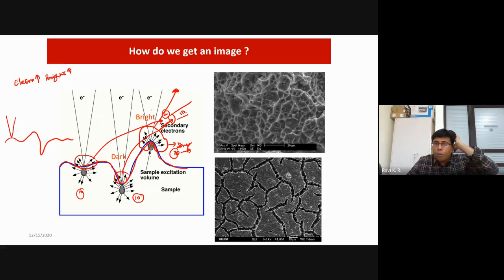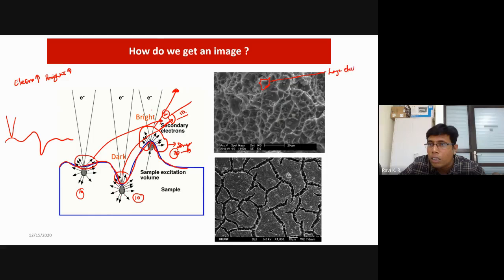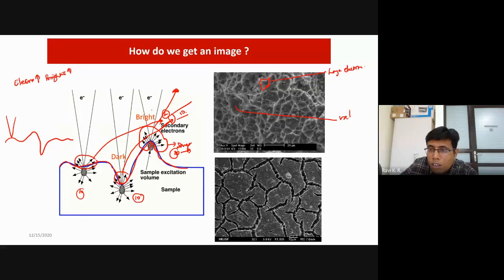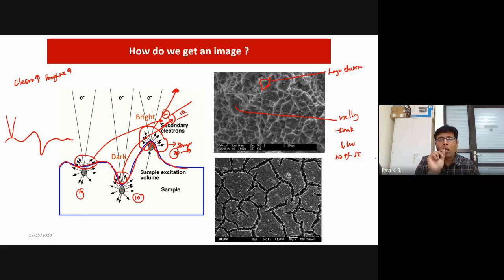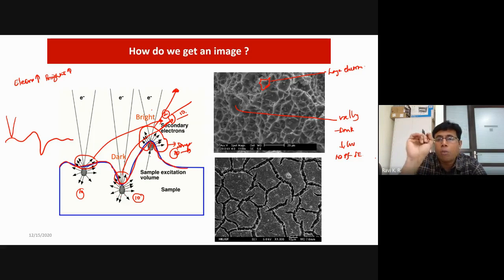The probability of electrons escaping is higher when the sample surface is at a peak. Peaks appear bright in the SEM image because you get a large number of secondary electrons. Valleys appear dark because fewer secondary electrons escape. Looking at an actual image — dark pits correspond to valleys where electrons get trapped, bright raised regions correspond to peaks. This is the basic contrast mechanism for secondary electron mode, which gives you morphological information.